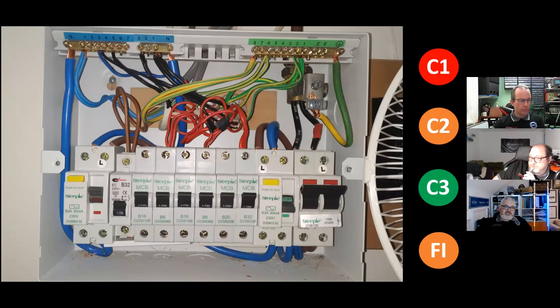Fixing detail, I would take that countersunk screw out rather than wait for someone to lean on that board and then have that board fall down and put all strain on that gland. But then again, in the same breath, I'd say that gland should be repotted, re-terminated with a new board or the board lowered. But you probably can't lower the board because of the method of installation, and it looks like it's mounted directly to plaster. So there's a level of stripping and rework that needs to be done there, which takes your improvement required into, if you don't do this, what is the actual risk?